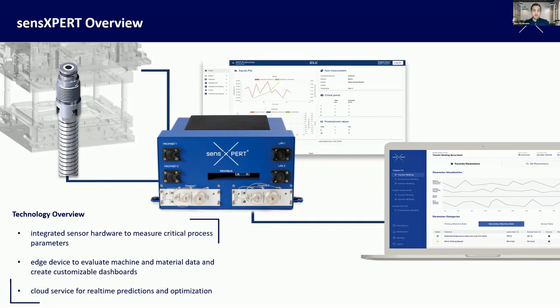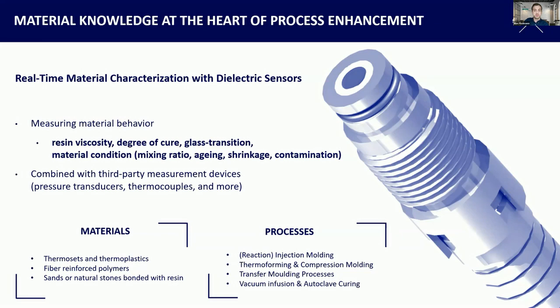Some of you are maybe very familiar with it, but it's a powerful measurement technique in that it can see a lot of different material behaviors: viscosity, degree of cure, glass transition temperatures. We combine it with third-party sensors, so pressure transducers and thermocouples. We focus primarily on thermosets, and we can do some thermoplastic measurements. We can measure fiber reinforced materials, composites, even conductive materials, across a range of processes - injection molding, compression molding, autoclave - really durable sensors that can be placed in the mold.